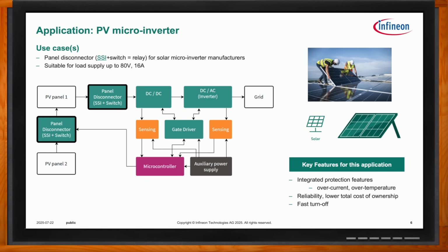And since the protection is integrated, there's no need for external fuses, which lowers cost and simplifies the design. The typical voltage and current for panel level electronics is 80 volts and 16 amps, which our SSI can work with. Just as important, being solid state means no moving parts, no wear out, and much longer lifetime compared to mechanical relays, which is critical when solar installations are expected to operate for decades without failure. This also reduces upkeep costs.